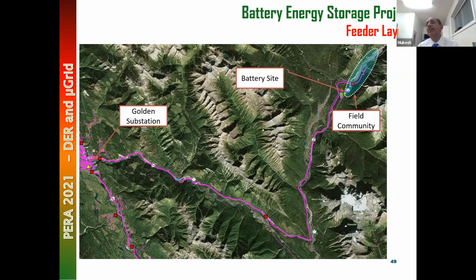But then an opportunity came, for a different reason. The substation transformer was supplying other loads. This station is supplying a load here. It's a very good resort area. There is some industry here. So the distribution station transformer had reached its peak. On a very cold day, the transformer loading was exceeding or approaching its maximum capacity. So basically, there was a need to replace the transformer to serve the peak load. And replacing a transformer is expensive.